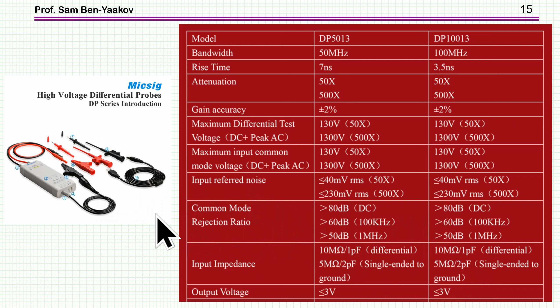Earlier we've seen 60 dB, so this is less susceptible to the common mode signal, 50 dB compared to the 60 dB. The impedance is 10 megohm in parallel with 1 picofarad. This is very, very nice. So this is another option.